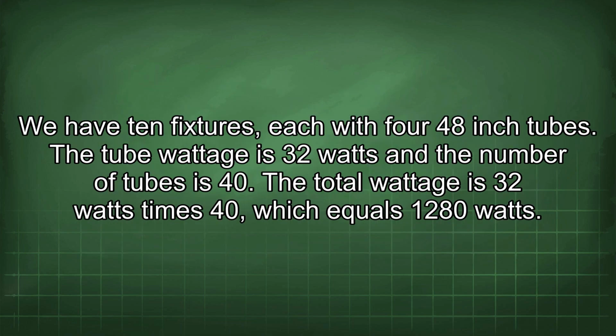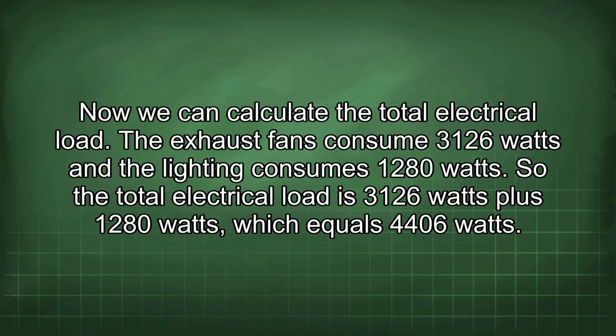We have 10 fixtures, each with 4 48-inch tubes. The tube wattage is 32 watts and the number of tubes is 40. The total wattage is 32 watts times 40, which equals 1280 watts. Now we can calculate the total electrical load. The exhaust fans consume 3126 watts and the lighting consumes 1280 watts.